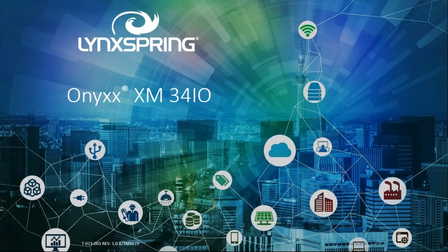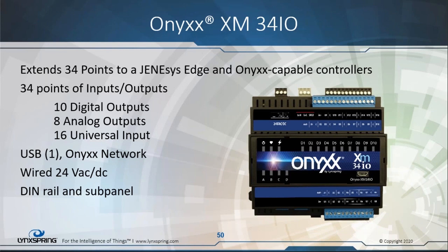Okay, quickly I'm going to go through Onyxx. Onyxx, like I said, is products that do not have Niagara, but they contribute to the JENEsys Edge products. Onyxx XM is simply a shell of an Edge 534, which has the same I/O, however it communicates to the Edge device through its Onyxx network - a proprietary CAN bus communicating network that enables an additional 34 points of I/O.